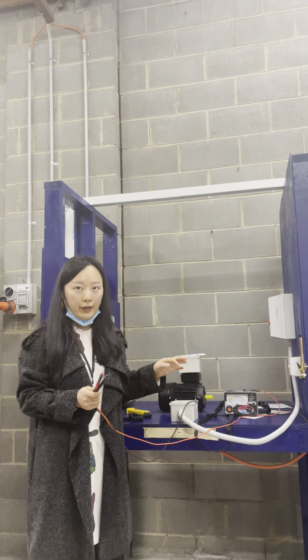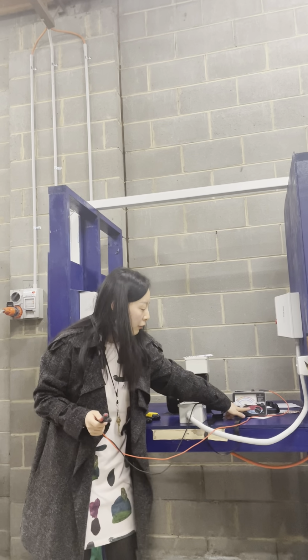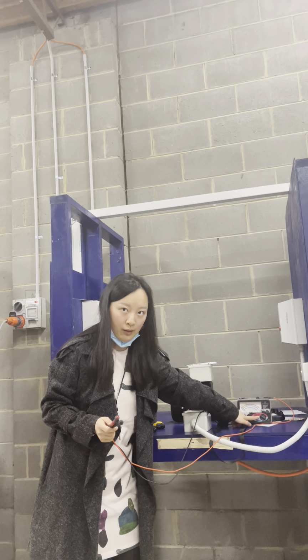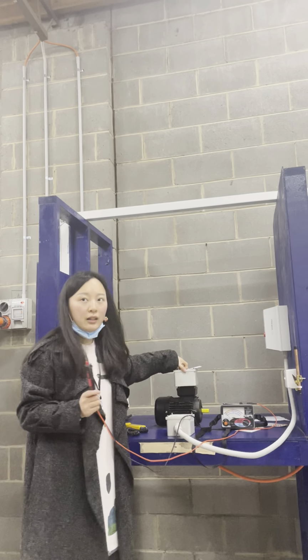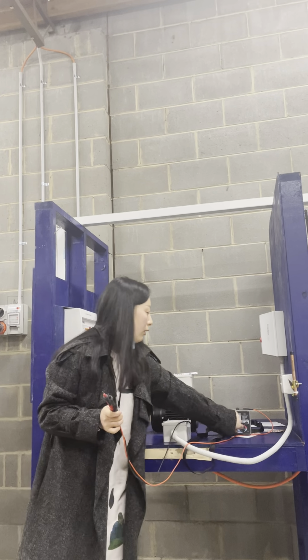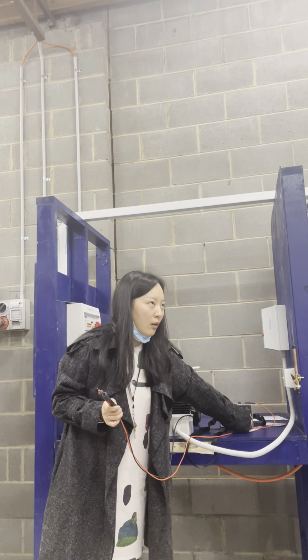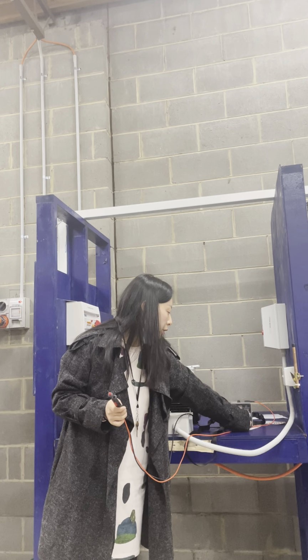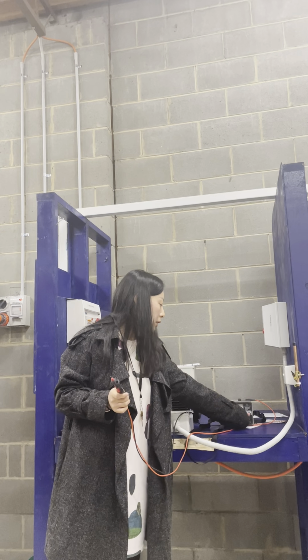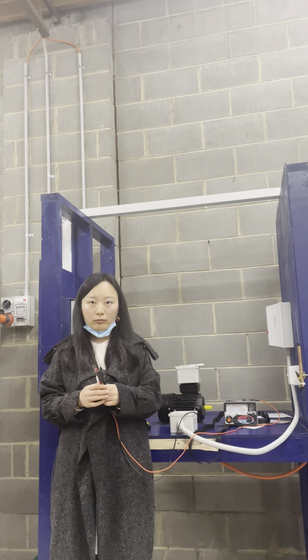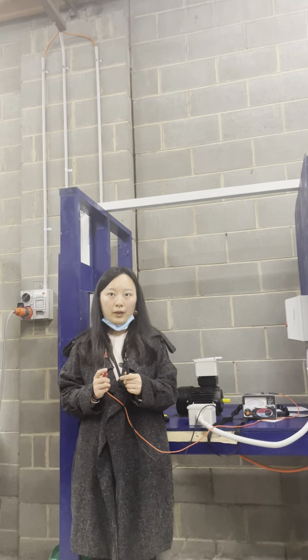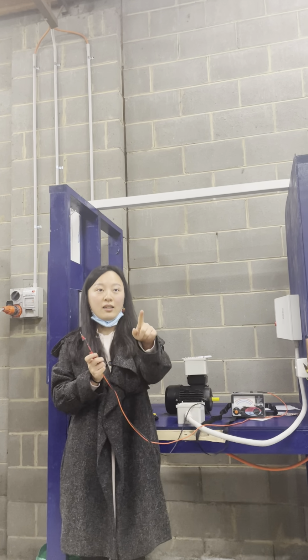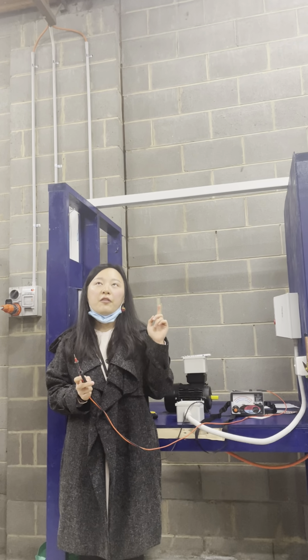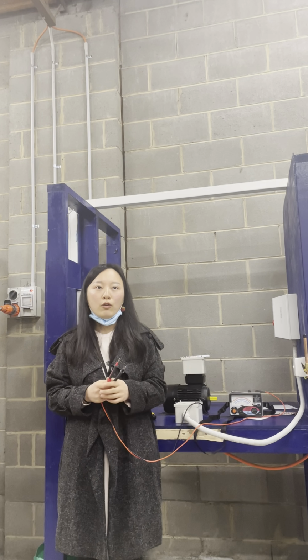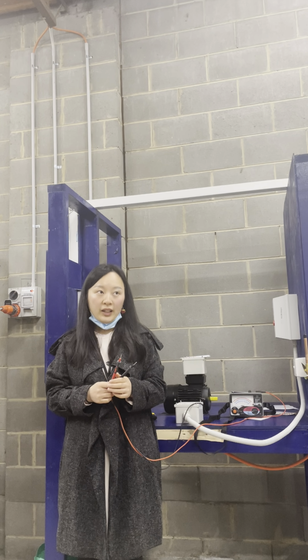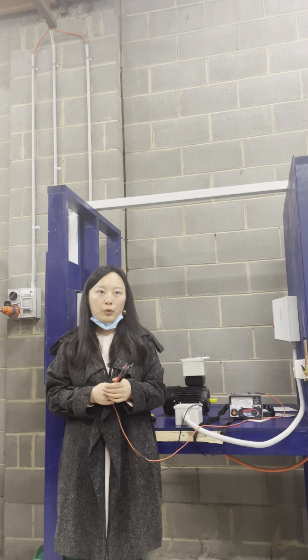So it doesn't matter 3-phase or single phase, you always use the 500 volts and 200 mega ohms. Okay? Does anyone know why? Why am I putting 500 volts, not 250 or 1000 volts? Because it's greater than 240 volts, so it's always safer. You need it double. Yes, that's the double. Now, if it is single phase, what's the supply voltage? 240. Yeah, 230, 240, whatever. So double it will be 500 volts.